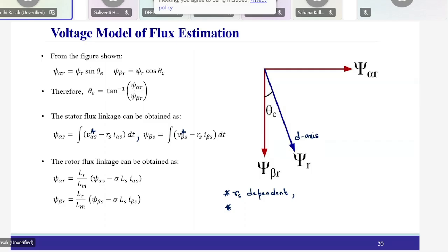So what we try to do is use a reference voltage, but at lower speeds, the reference voltages may not be directly replicated by the VFD, because of dead-time effect and the nonlinearity of the switches. There is some problem. So that's why we try to avoid direct vector control and rely on the current and the speed for implementing indirect vector control.